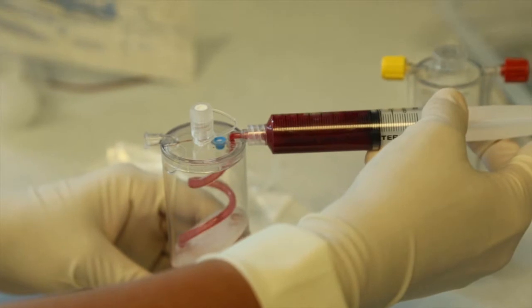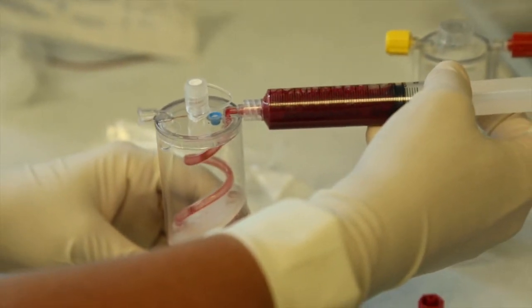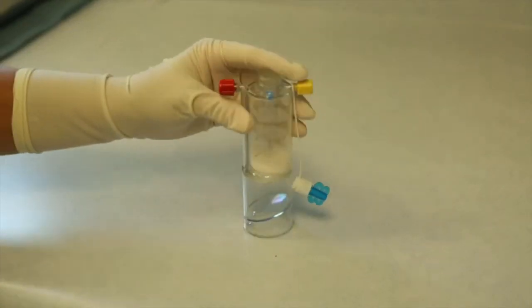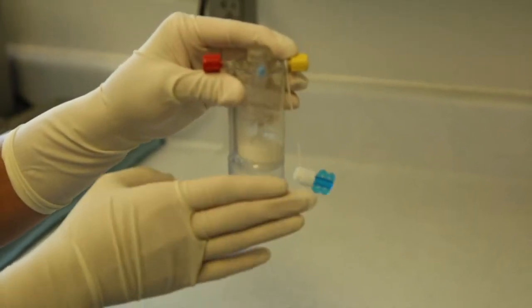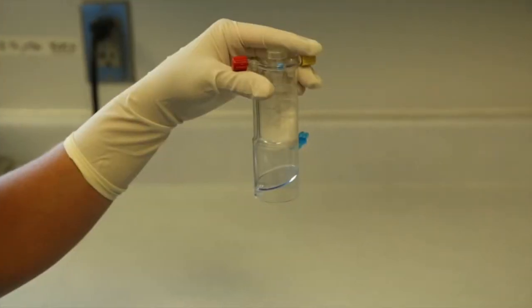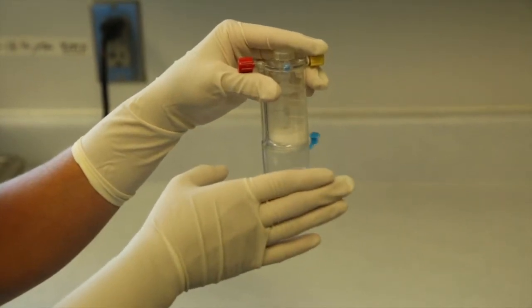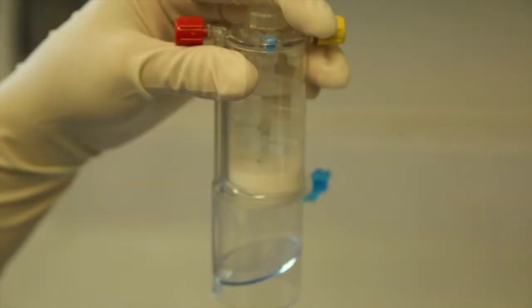Withdraw about 2 mL of the platelet-rich cell suspension into the syringe and shake the remaining platelet-rich cell suspension in the device with the syringe attached for about 30 seconds to ensure appropriate suspension of the cells. Withdraw the remaining platelet-rich cell suspension. Take out the concentrator device, the second device with the beads, and ensure that the beads are evenly distributed across the bottom surface. You can gently shake or tap the device to achieve this. At the time of loading the platelet-rich cell suspension, this even distribution of beads helps to limit premature leakage to the lower part of the device.